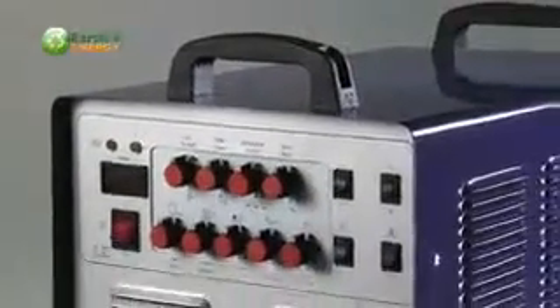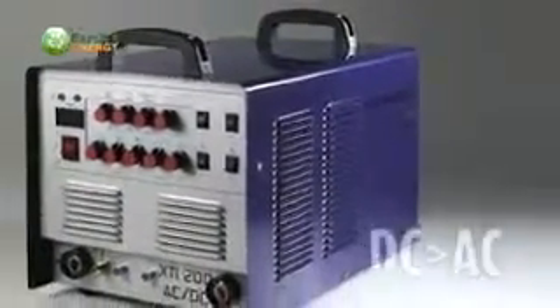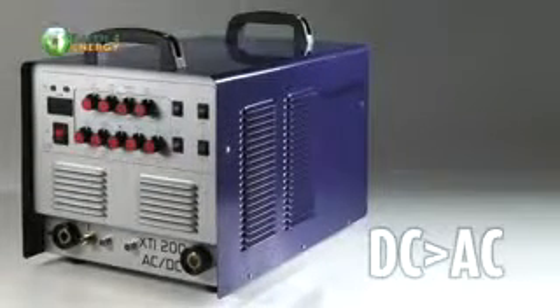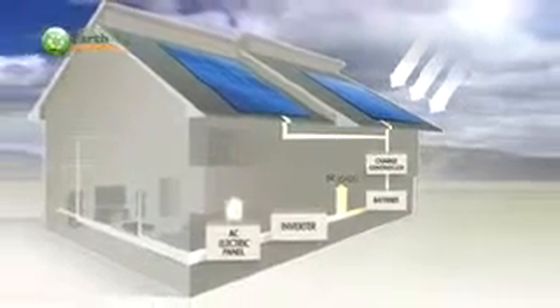The next system we'll talk about is an off-grid system with a generator. This is like the previous one, which is completely off-grid. However, you'll notice that this one is a little more elaborate. We have the same PV panel, and just as before, the energy goes to a charge controller, which in turn forwards it to the storage battery or battery bank, depending on the size of your system. From the storage battery, the power goes to the inverter. Now, an inverter, as we talked about earlier, is the device that actually takes the DC or direct current and converts it to AC or alternating current, so we can use it in our home. So the inverter passes voltage up to the AC electric panel.